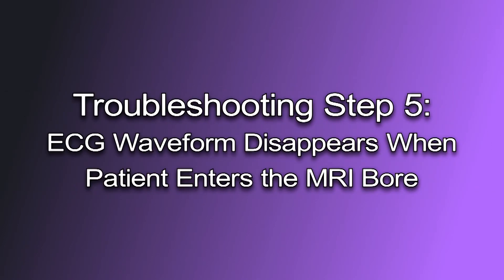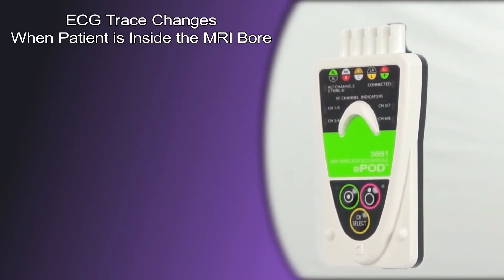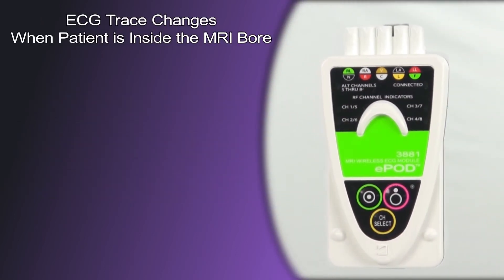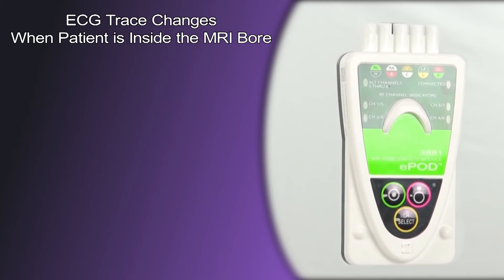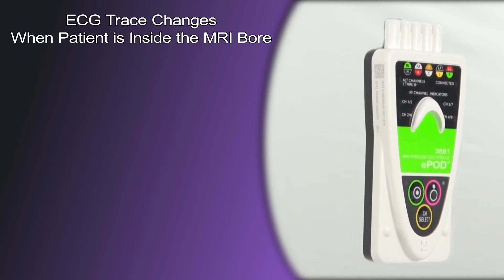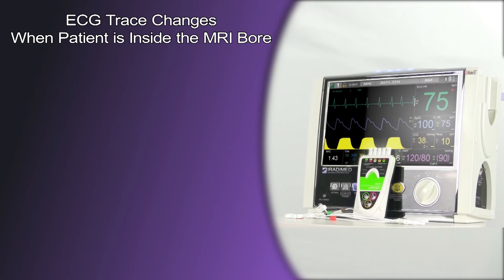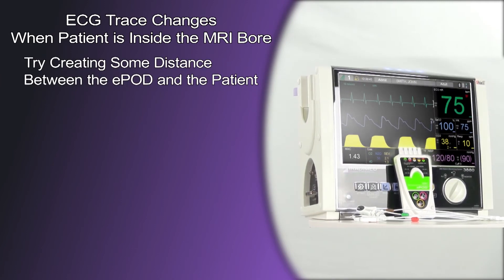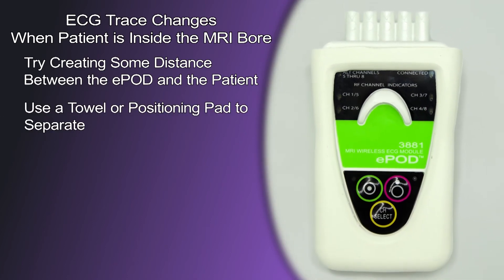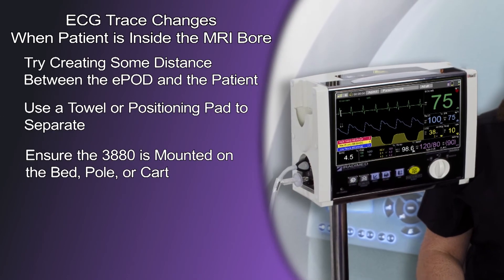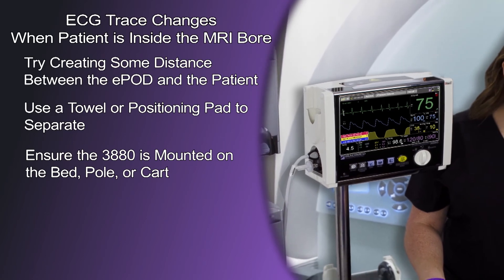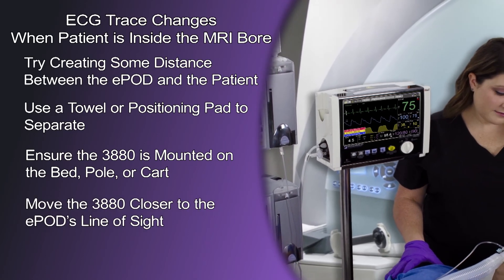Troubleshooting Step 5: ECG waveform disappears when patient enters the MRI bore. It is possible that certain MRI systems can disrupt the wireless signal between the ePod and the 3880, causing enough signal delay that the ECG trace will not be displayed. Some human bodies can absorb RF, so try creating some distance between the ePod and the patient — use a towel or positioning pad to separate. Ensure the 3880 is mounted on the bed, pole, or cart, and move it closer to the ePod's line of sight.